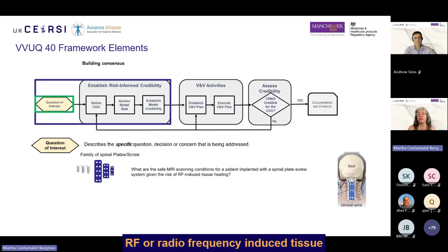So the standard framework introduces a structured process consisting of the following key elements. First is the question of interest, which describes, as Steve said, the specific question or decision of concern that is being addressed. The model must address a clearly defined decision or regulatory question, such as demonstrating device safety, predicting clinical performance, replacing a bench test, supporting a design optimization, for example, or evaluating labeling claims. The intended regulatory or engineering decision drives all subsequent credibility requirements. Here is the question of interest that simulation will address in the example: What are the safe MRI scanning conditions for a patient implanted with a spinal plate screw system, given the risk of RF, or radiofrequency-induced, tissue heating?